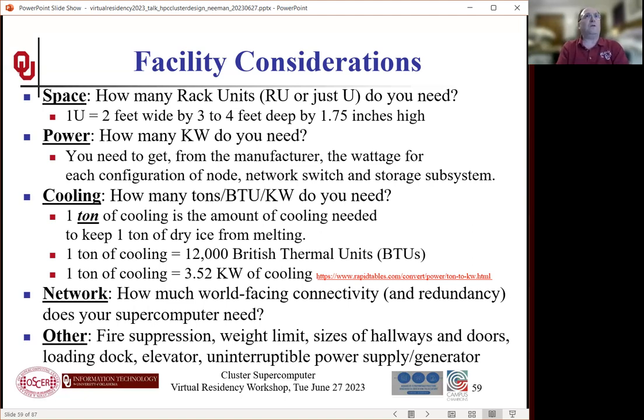I think we're something like 2,000 pounds per square foot on the pedestal flooring we have. You have to take that into account, look at what's in the nodes in your racks and how many nodes there are, and whether you're going to exceed the weight tolerance those floor tiles have.